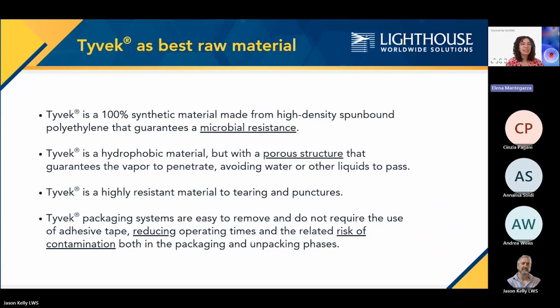So Tyvek is a 100% synthetic material made from high-density spunbound polyethylene. So it's constituted of continuous fibers. And this structure guarantees microbial resistance. So we have the first answer, permeability. Microbial resistance is a barrier. Then Tyvek is a hydrophobic material, but has a porous structure that allows vapor to penetrate, avoiding water, liquids, or also solids passing through. So we have a barrier.